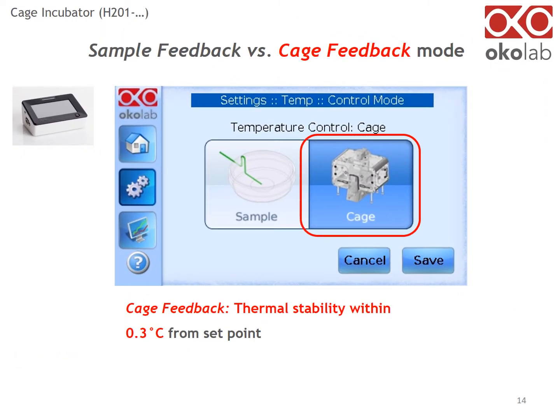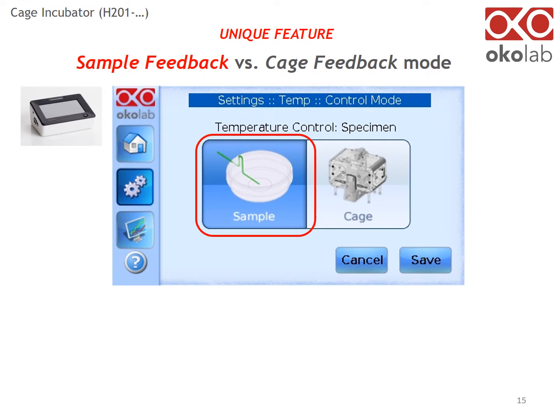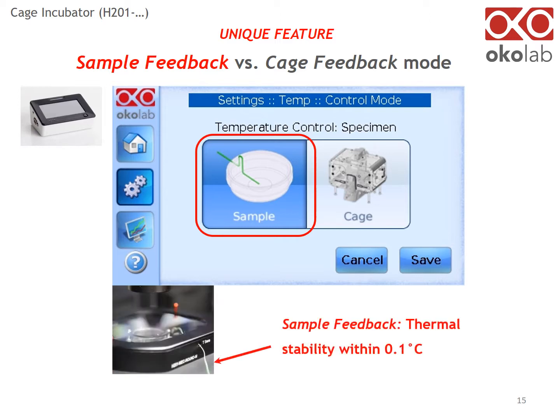Operation in cage feedback mode offers thermal stability within 0.3 Celsius from your set point. Additionally, you can operate in sample feedback mode by inserting a thermocouple in a reference well. Operating in sample feedback mode ensures thermal stability within 0.1 Celsius from your set point.